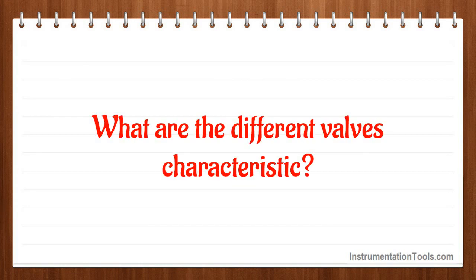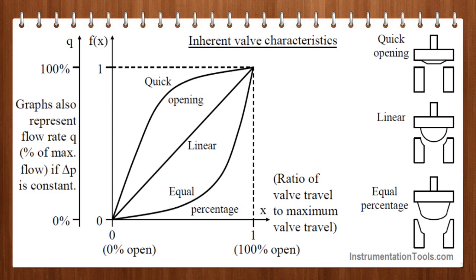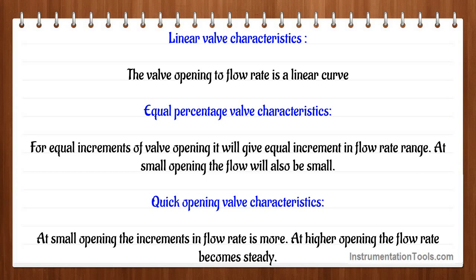What are the different valve characteristics? The different types of valve characteristics are linear, equal percentage, and quick opening. For linear valve characteristics, the valve opening to flow rate is a linear curve. For equal percentage valve characteristics, equal increments of valve opening give equal increments in flow rate range — at small opening the flow will also be small. For quick opening valve characteristics, at small opening the increments in flow rate are more, while at higher opening the flow rate becomes steady.